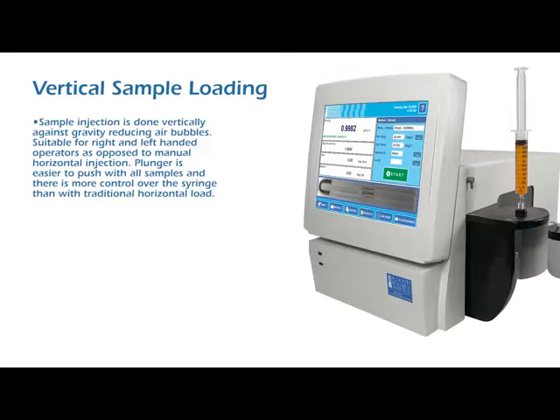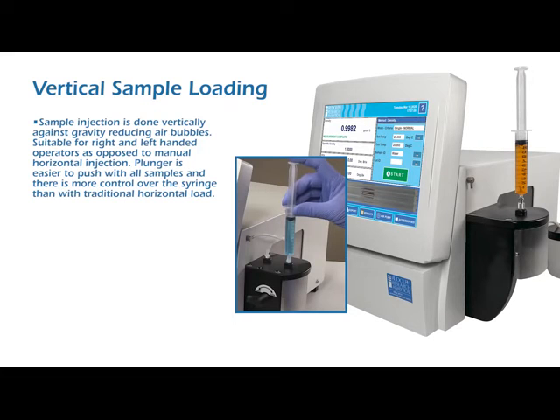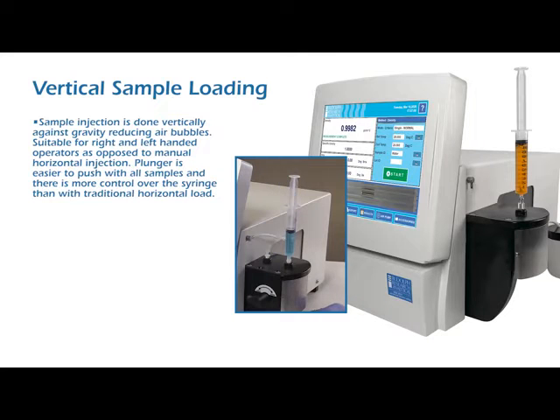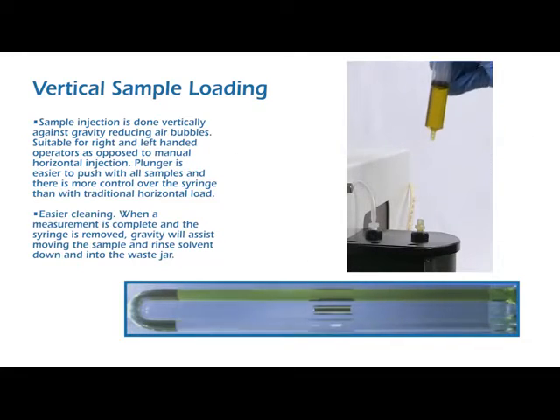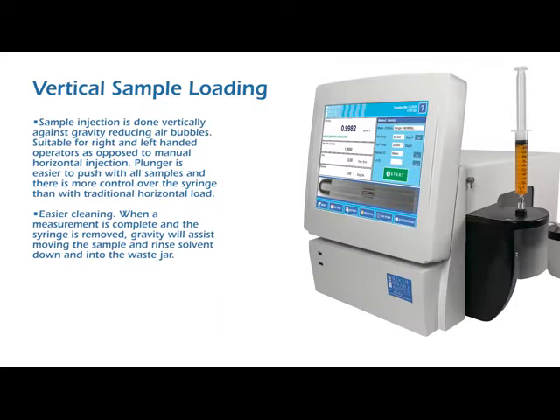Vertical sample loading: sample injection is done vertically against gravity, reducing air bubbles. Suitable for right and left-handed operators as opposed to manual horizontal injection. The plunger is easier to push with all samples and there is more control over the syringe than with traditional horizontal loading. Easier cleaning: when a measurement is complete and the syringe is removed, gravity will assist moving the sample and rinse solvent down and into the waste jar.